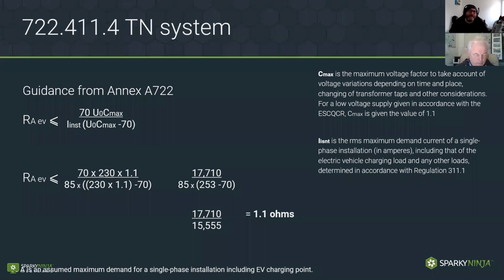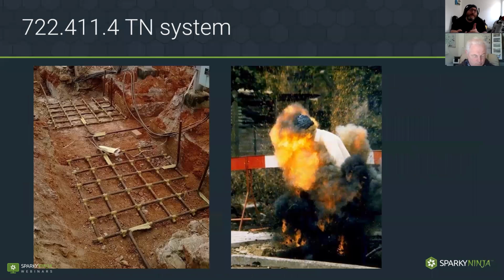And the other thing is obviously driving the electrode down. If we can avoid that by installing devices, then you're going to see people show you things like the risks of driving spikes into the ground and having arc flashes occur. We could potentially break through and hit underground service cables, and that's something we should try to avoid. So we've got two areas that will complain about the impracticality of this little regulation. It's hard to achieve the low enough RA, and there is an increased level of risk driving electrodes down. So that's the second option here, the idea of putting an electrode in. These are both from the old 18th edition.